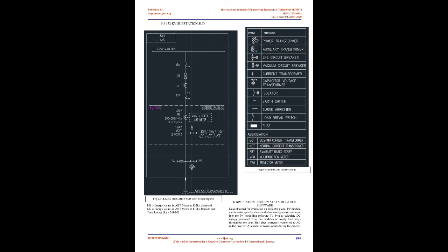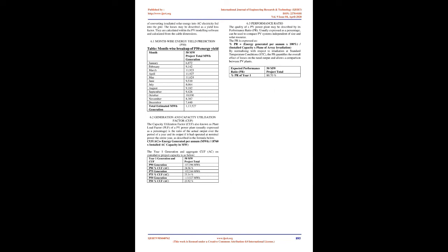6. Simulation using PVSYST simulation software. Data obtained for irradiation on collector plane, PV module and inverter specifications, and plant configuration are input into the PV modeling software PVSYST to calculate DC energy generated from the modules in hourly time steps throughout the year. This direct current is converted to AC in the inverter. A number of losses occur during the process of converting irradiated solar energy into AC electricity fed into the grid. The losses may be described as a yield loss factor. They are calculated within the PV modeling software and calculated from the cable dimensions.